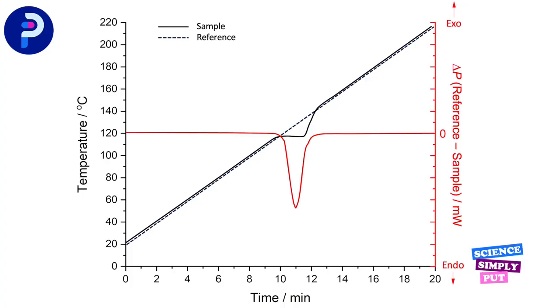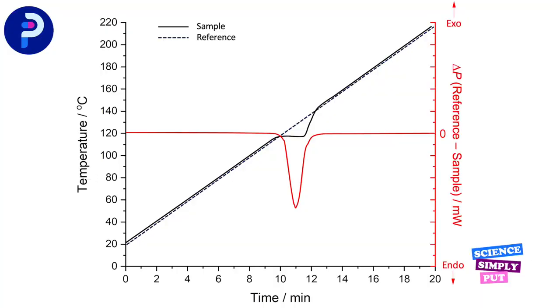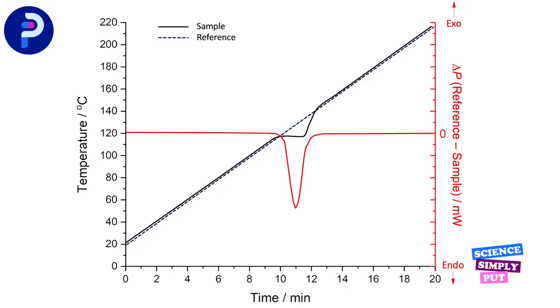If we were to plot a graph showing the sample and reference temperatures as a function of time, and also looked at the difference in power being supplied by the furnaces, we would see something that looks like this, as we discussed in the previous video. While the sample is not doing anything, it will heat at the same rate as the reference. But when it starts to undergo a phase transition — in this case melting — the sample remains at one temperature while the reference continues to heat up. The instrument, which is programmed to heat both sample and reference at the same rate, notices there is now a temperature difference between the sample and reference, and acts to drive the temperature of the sample back to that of the reference by supplying more power. The extra power supplied to the sample is what is plotted on our DSC graph.